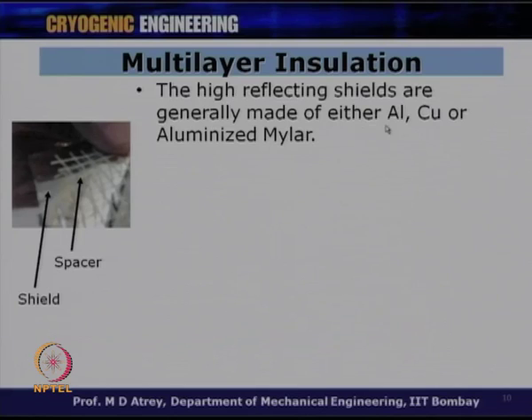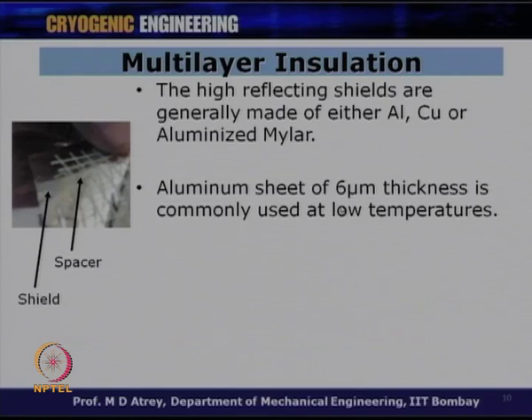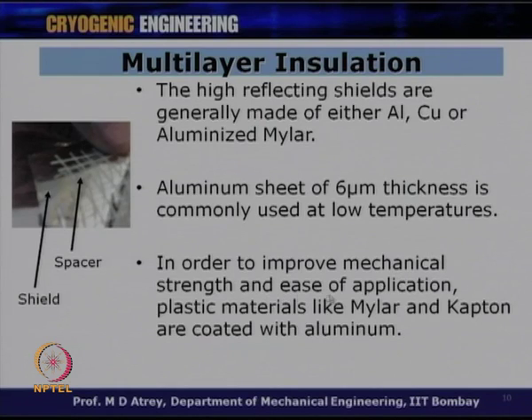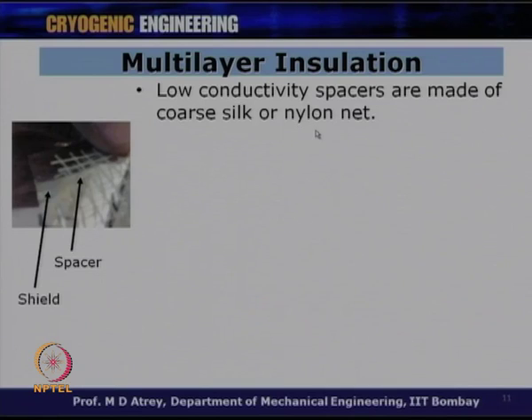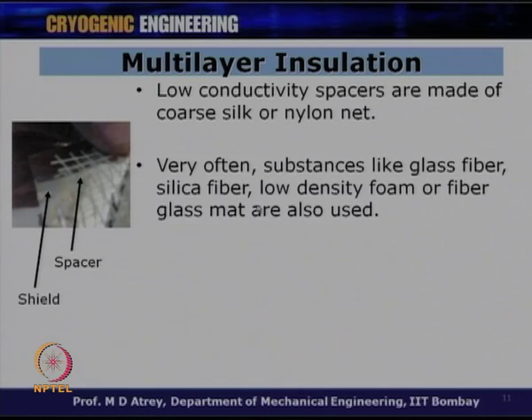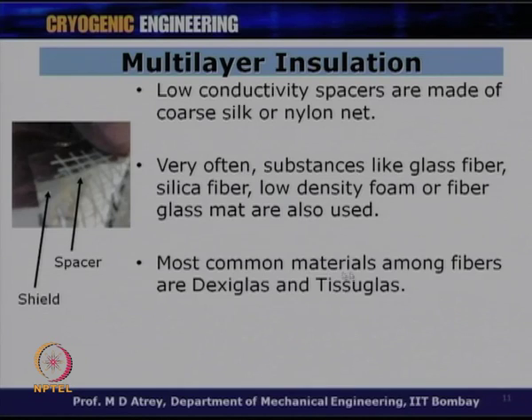The high reflecting shields are generally made of aluminum, copper, or aluminized mylar. Aluminum sheet of 6 micrometer thickness is commonly used at low temperatures. Plastic materials like mylar and kapton are coated with aluminum to improve mechanical strength. Low conductivity spacers are made of coarse silk or nylon net. Substances like glass fiber, silica fiber, low density foam, or fiberglass mat are also used as spacers.